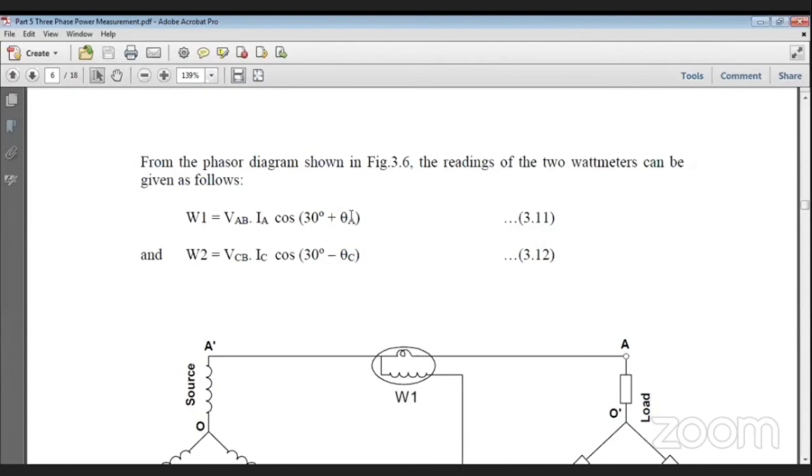Now, negative reading, how do we get it? Earlier we had a problem because all those were analog meters. Today you have no problem. These will all be digital wattmeters. So you will clearly get that W2 is reading plus 100, W1 is reading minus 20. Now what is your decision? That this wattmeter has gone crazy. This is totally crazy reading. But the fact is not that. It is not crazy. It is quite plausible, technically possible readings.